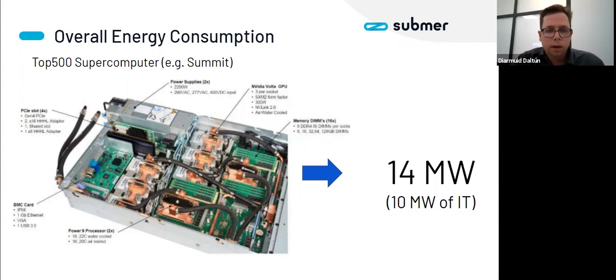What's quite obvious is that this is an image of a liquid-cooled node, exactly what's deployed at Summit. These nodes have pipework and cold plate heat sinks used to remove heat from the systems. One of the challenges is the complexity of all this pipework and the additional cost of these specially designed heat sinks and cold plates, which we'll dig into during this webinar. Just briefly on the number to the right, Summit is approximately 14 megawatts in total, cooling plus compute, and 10 megawatts of that is the pure compute.